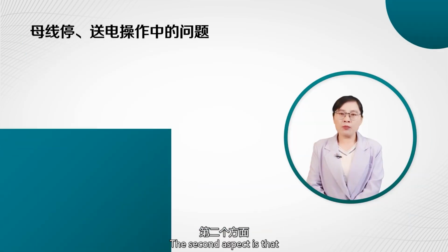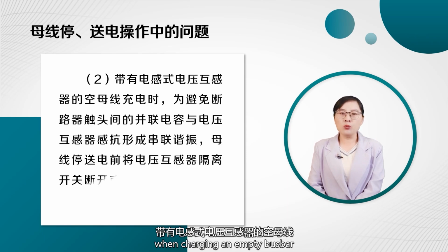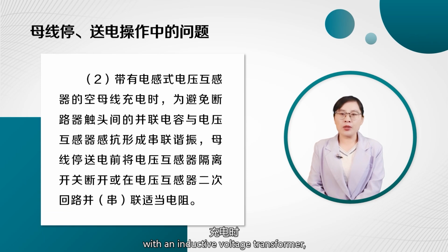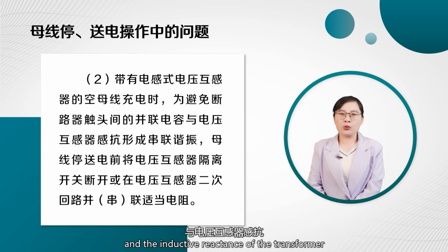The second aspect is that when charging an empty busbar with an inductive voltage transformer, it should be avoided that the parallel capacitance between the circuit breaker contacts and the inductive reactance of the transformer form a series resonance.